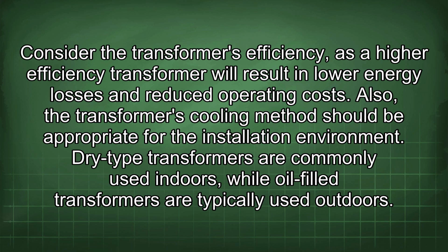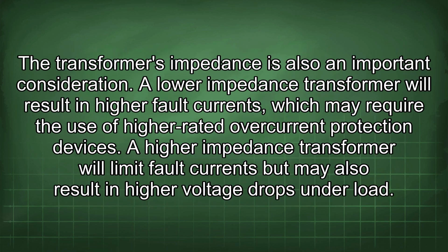Dry-type transformers are commonly used indoors, while oil-filled transformers are typically used outdoors. The transformer's impedance is also an important consideration. A lower impedance transformer will result in higher fault currents, which may require the use of higher rated overcurrent protection devices. A higher impedance transformer will limit fault currents but may also result in higher voltage drops under load.